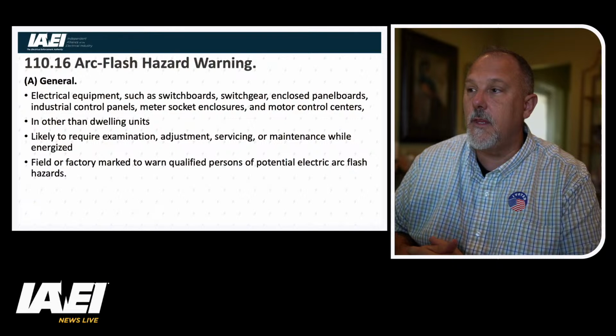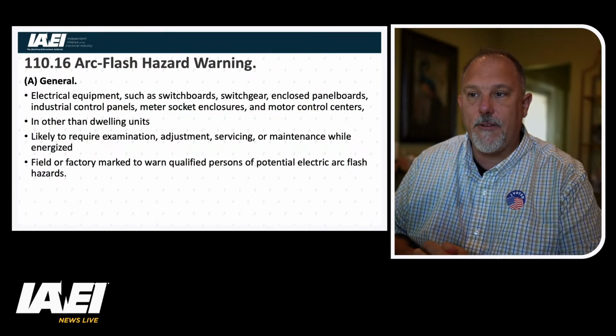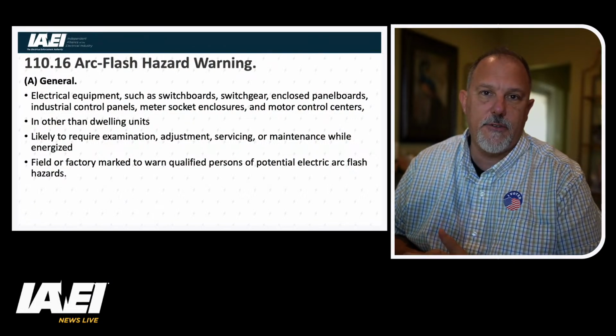And motor control centers in other than dwelling units likely to require examination, adjustment, servicing, or maintenance while energized. So you have to put that arc flash hazard warning on that equipment that is likely to require examination, adjustment, servicing, or maintenance while energized. It can be field or factory marked.